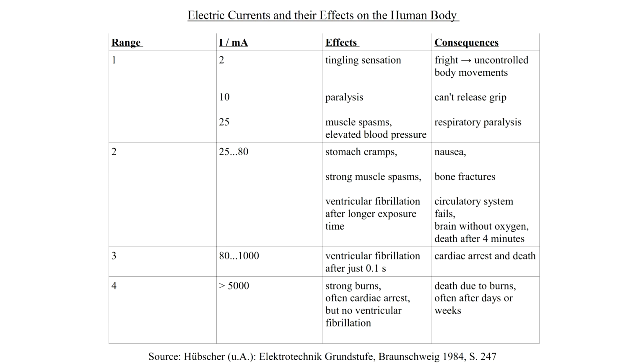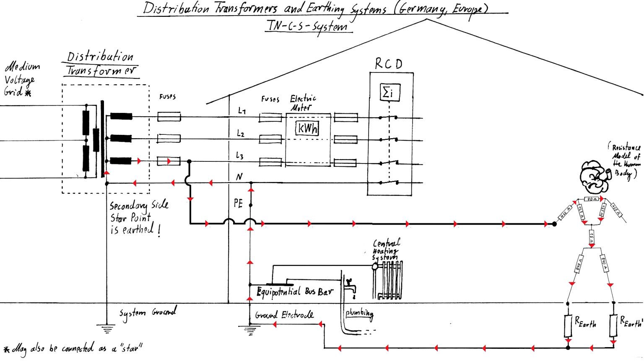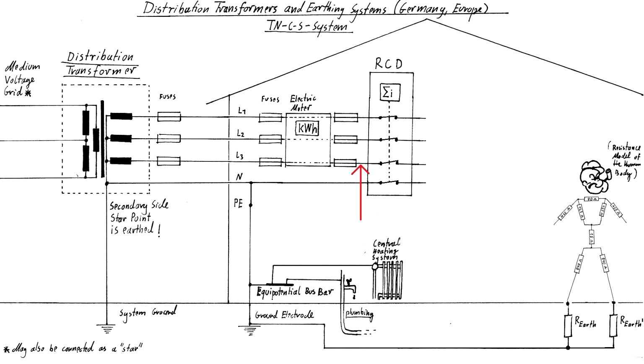To better understand this, let's take a look at this picture. Let's say a human was to have contact to one of the phases out here directly. The current would flow from the distribution transformer secondary through the overhead line into his body and through the legs to the earth, where it would flow through the ground to the ground electrode, from there via the PE conductor and over the combined PEN conductor back to the transformer secondary. In this case, the fact that the star point is connected to earth becomes a curse to the poor guy because it closes the electric circuit via the ground he is standing on. The same thing would happen if he had touched the line here or here. The current ratings of all these fuses are much too high to help him out.